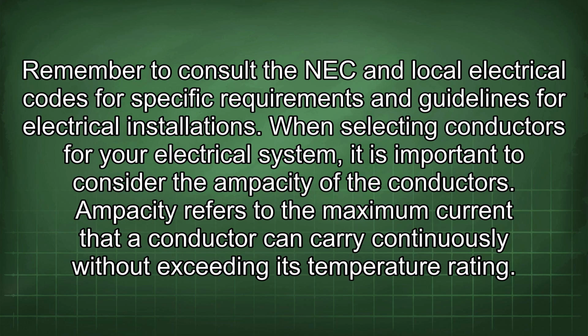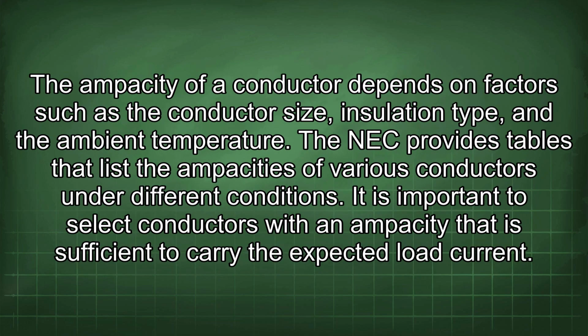When selecting conductors for your electrical system, it is important to consider the ampacity of the conductors. Ampacity refers to the maximum current that a conductor can carry continuously without exceeding its temperature rating. The ampacity of a conductor depends on factors such as the conductor size, insulation type, and the ambient temperature. The NEC provides tables that list the ampacities of various conductors under different conditions.